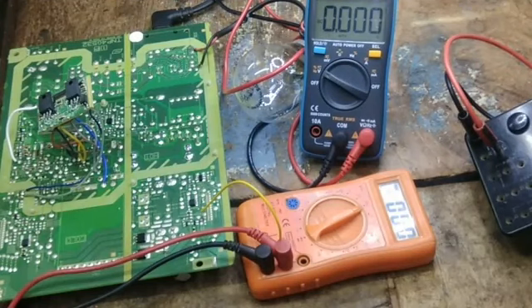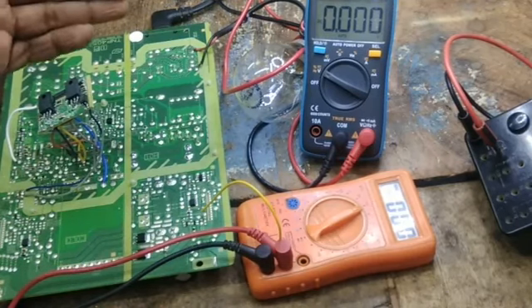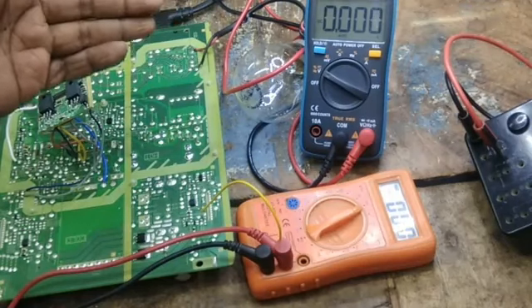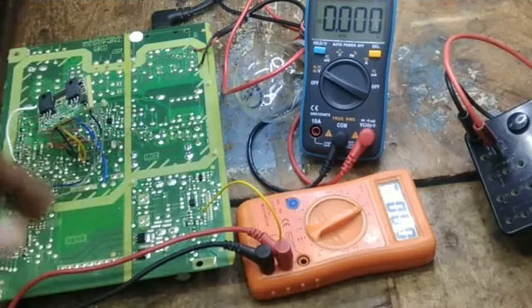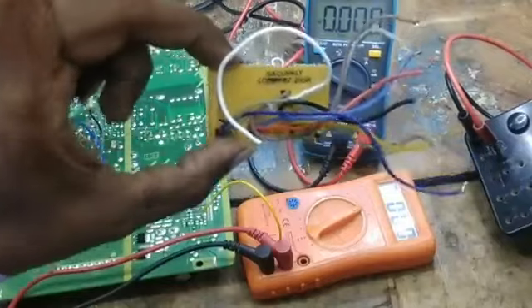In standby mode, the LLC power supply only gets started with low ampere. After that, whenever we release from standby to on mode, the main filter capacitor voltage will be 390 or 395 voltage. Only after that does this module start to work. The design is like that.